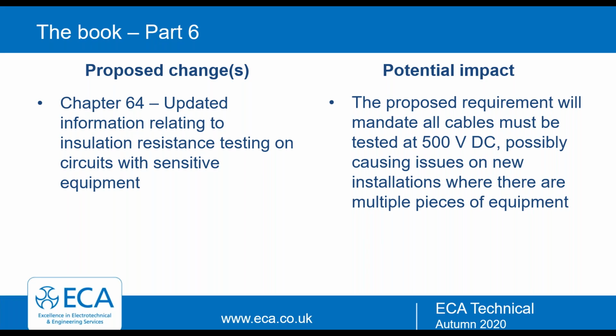If you've got connected equipment, then you tend not to test it at 500 volts, because you could cause damage to the sensitive equipment that's attached to that circuit - LED lights, USB socket outlet type things, these could potentially cause issues. So if there's any members out there doing a lot of inspection and testing work on new installs, that might be something to comment upon.